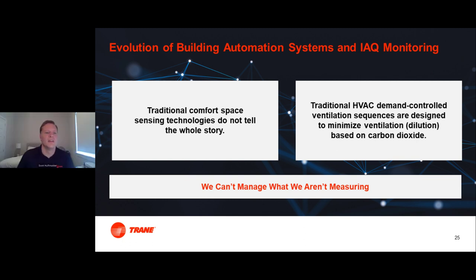Thank you, Jeff. So Scott Huffmaster here, going to talk a little bit about the impact to automation systems and monitoring, what we're seeing as market trends. Historically, we had traditional sensors that would tell us temperature, humidity potentially, and in some instances CO2. Traditionally, we would use that data to do control sequences like demand control ventilation. But a lot of this is, of course, based upon the premise of reducing energy use for the building.